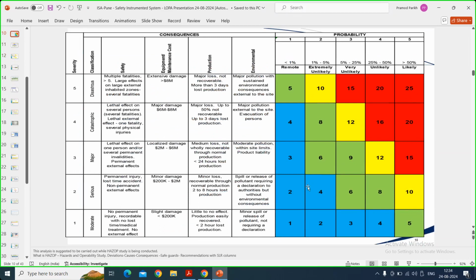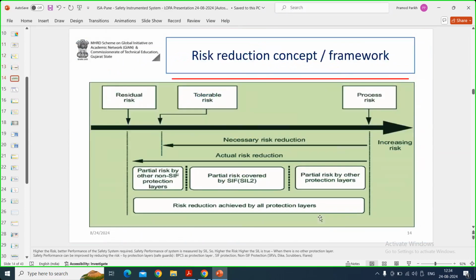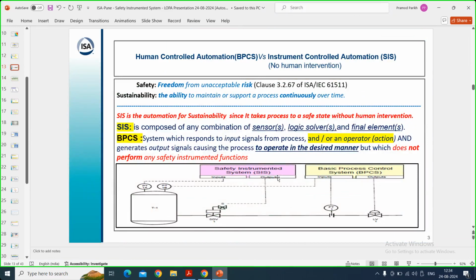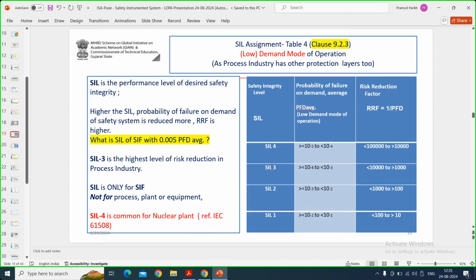What SIS is doing is reducing the risk beyond BPCS. BPCS alone cannot reduce the risk. When your BPCS alone cannot reduce the risk, you go for a separate independent system. And maybe SIL 1 also will be okay for the lifetime of the plant. You don't have to always go to SIL 2 or SIL 3 design. So it all depends upon proper HAZOP.